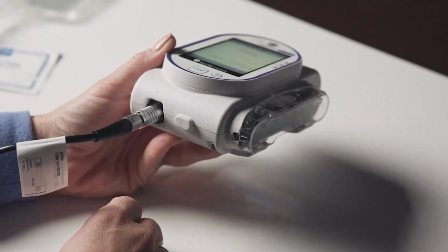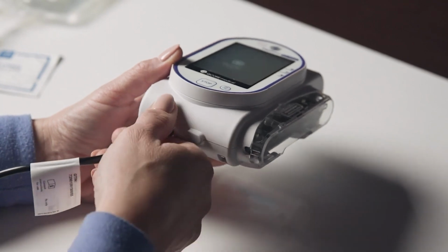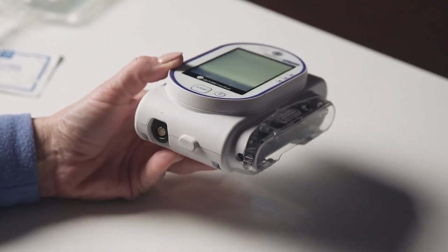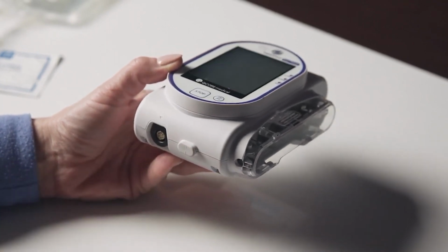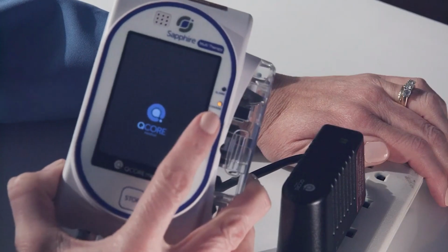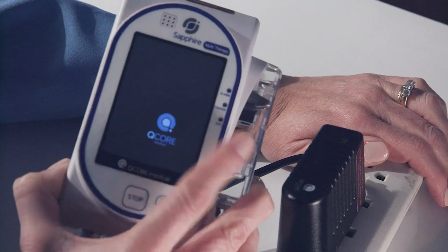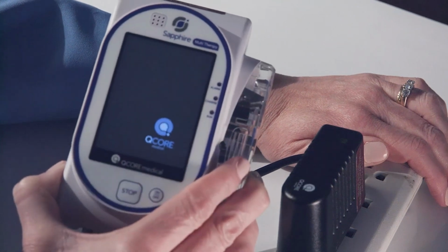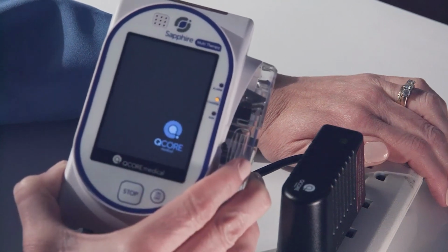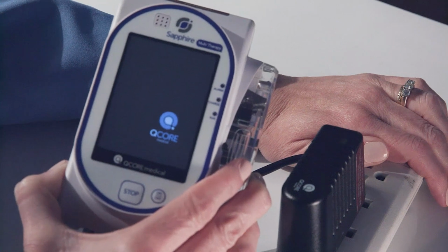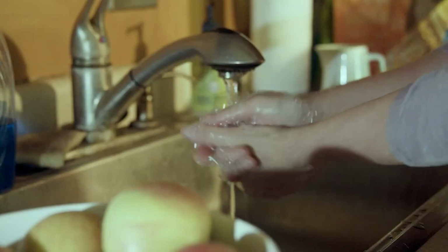When charging is complete, remove the power cord from the pump by grasping the metal connector close to the pump and pulling straight out. It is recommended that you have the pump plugged in and charging while your infusion is running as often as possible. Your Sapphire pump must be plugged in for a minimum of 6 hours a day to maintain its charge.